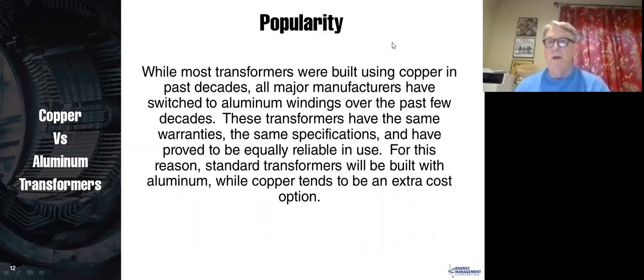And obviously, as that change was made, there were people wondering and asking questions about whether that was going to decrease the reliability of the transformers. Well, it turned out that was kind of a nothing to us. The aluminum transformers work just fine, and they have the same warranties, they have the same specifications, and over the ensuing decades, our aluminum transformers turned out to be equally reliable in use. As you know, transformers are pretty reliable devices. They tend to last for decades. And so for this reason, everyone switched to aluminum, and that is their standard design. And they can build you a copper one, but it tends to be extra cost and special order because their standard design is aluminum. And that pretty much is still the situation with your high volume, large, very popular manufacturers.